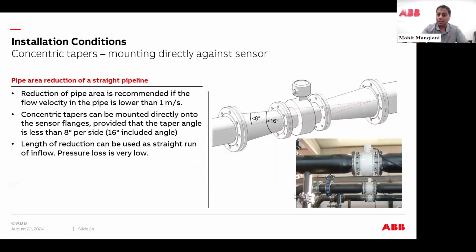Concentric tapers. Another option is that you can put reducers right next to the mag meter. Most people, as I mentioned earlier, if I have a 10-inch pipe, I can typically install a 10-inch valve and a 10-inch mag meter, and I'll get good accuracy. The challenge becomes if the velocity inside the piping, due to increased viscosity or increased conditions of the process, is low, you might need to go to a smaller mag meter to get increased velocity to get the accuracies you need. So if you want to install a concentric taper on the upstream and downstream of the mag meter, this is perfectly acceptable.